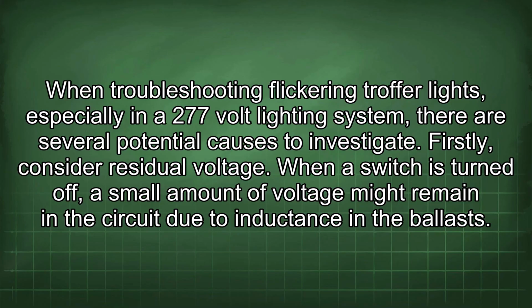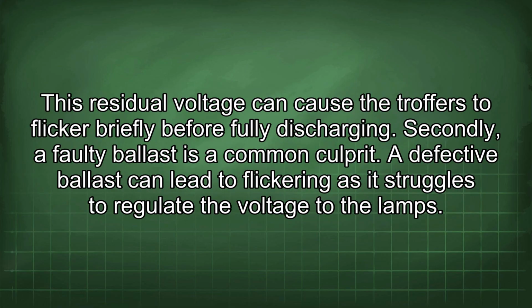When troubleshooting flickering Troffer lights, especially in a 277-volt lighting system, there are several potential causes to investigate. Firstly, consider residual voltage. When a switch is turned off, a small amount of voltage might remain in the circuit due to inductance in the ballasts. This residual voltage can cause the Troffers to flicker briefly before fully discharging.